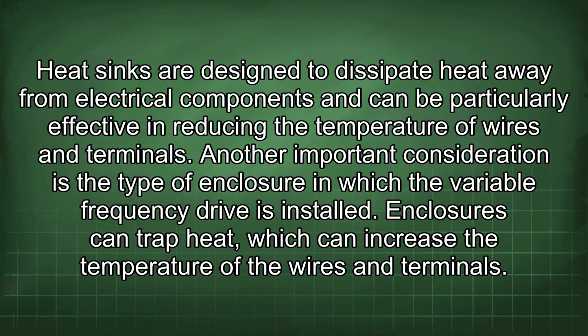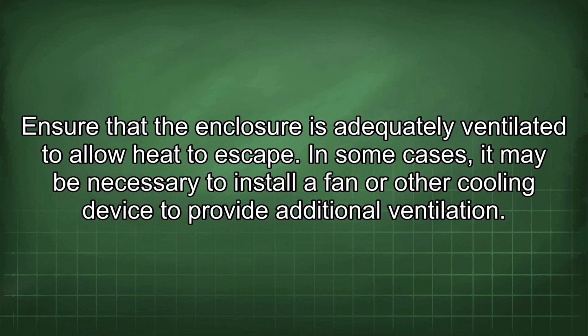Enclosures can trap heat, which can increase the temperature of the wires and terminals. Ensure that the enclosure is adequately ventilated to allow heat to escape. In some cases, it may be necessary to install a fan or other cooling device to provide additional ventilation.